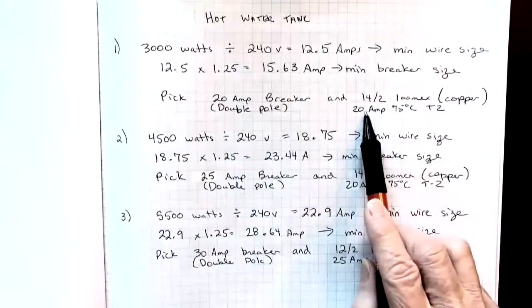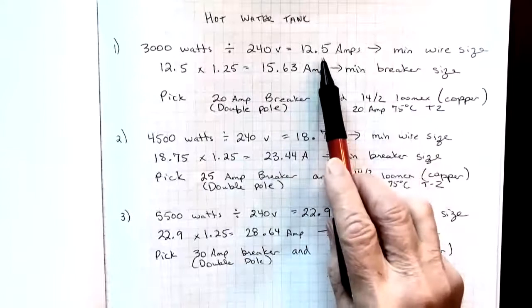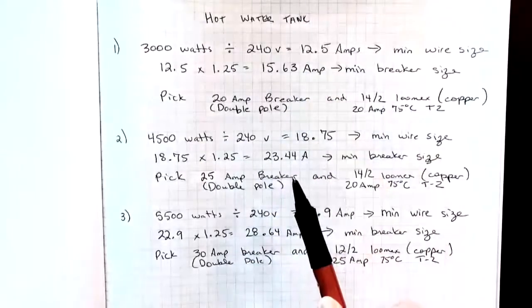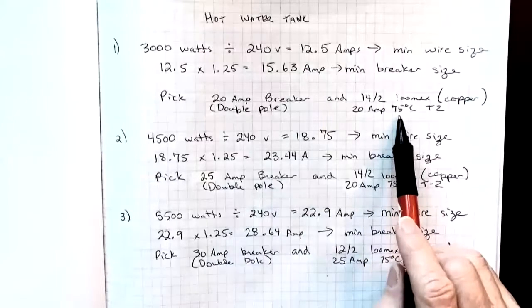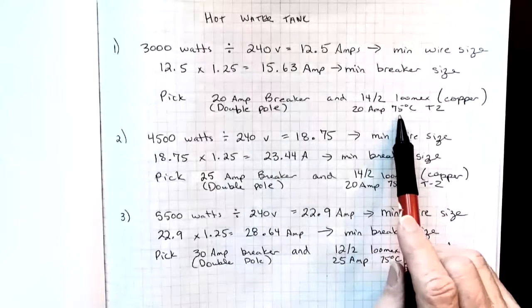If we go to table two, we'll see that it's good for 20 amps in the 75 degree column and we only needed 12.5 amps to cover this load. One thing to check is that the equipment is actually rated for 75 degrees at the terminations.